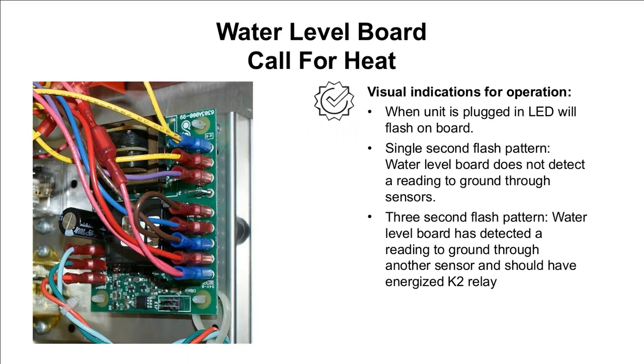These sensors engage to a water board. The water board is, again, connected to supply power. When the unit is plugged in, it receives power. You can see this as a good visual ID with a small LED. It will flash when the unit has power. A single-second flash is telling you the water board is not detecting water through the sensors. A 3-second flash is telling you that the water board does detect water, and it should be accepting the call to heat.